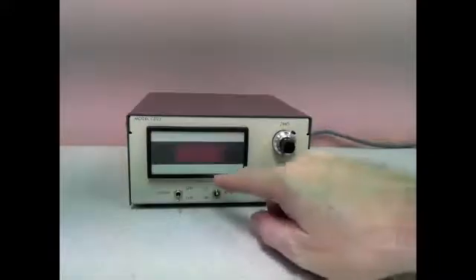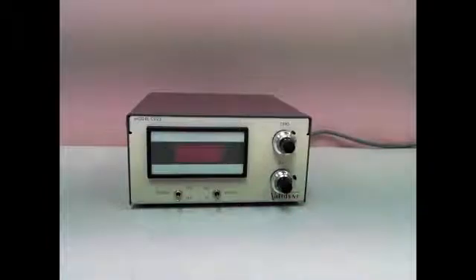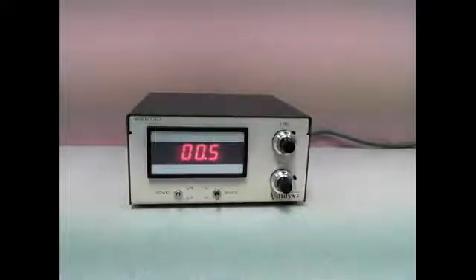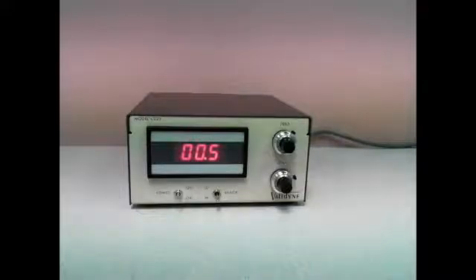Set the CD23 range switch to high. Turn on the CD23 by throwing the power switch to on. The digital display will light up. The standard CD23 display will indicate a reading in percent from 0 to plus or minus 100.0%. The 100.0% indication corresponds to the plus 10 VDC analog output signal. When the CD23 is powered, it should read near 0%.